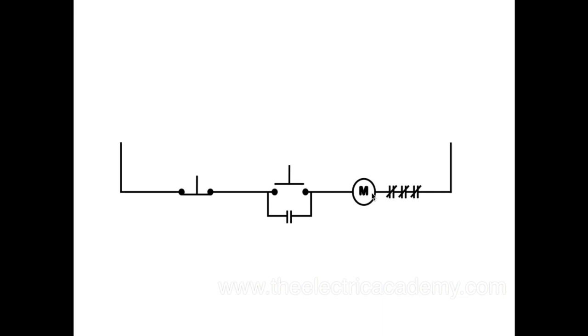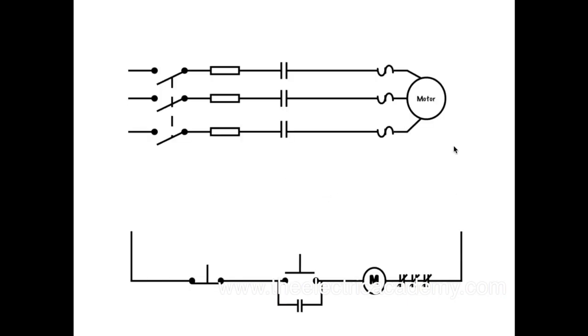We push that down, M coil - that's not the motor, that is a coil - energizes, goes through the overloads. At the same time that M coil energizes, these contacts close and it holds in. So if I let go of the start button, this will go all the way through and I'm good to go.